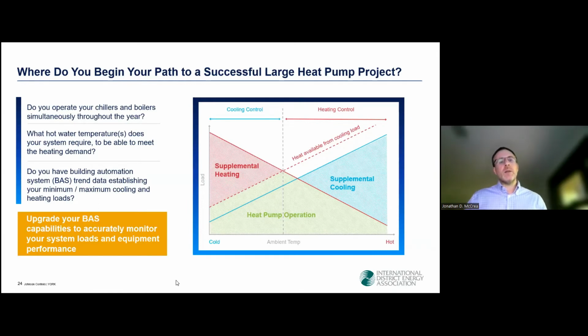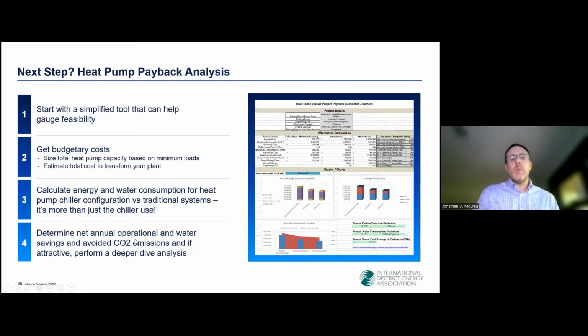All right, so if we move on beyond the loading graph, manufacturers and consulting engineers often will have a first pass, high level heat pump analysis tool that will help you get a good approximation of the net operating cost savings and also your sustainability benefits. The heat pump analysis tool to the right has inputs for a lot of different things, including minimum and maximum cooling and heating loads, natural gas rates, electricity rates, and a budgetary project cost as well. It will give you a payback analysis with annual operating cost savings broken down into the different components, and then your CO2 emissions reductions as well as your water savings.